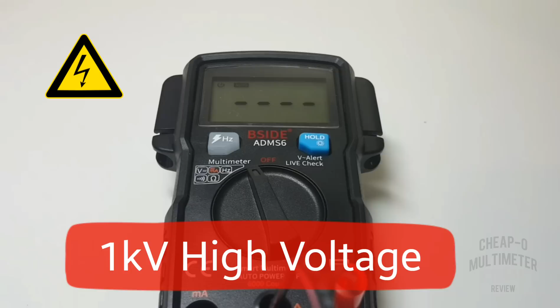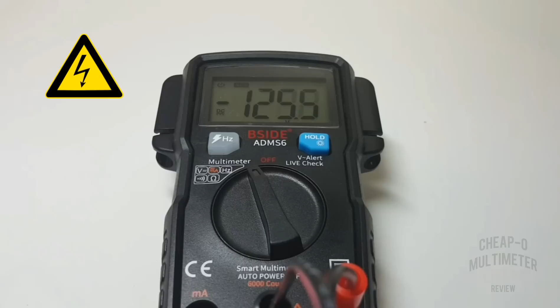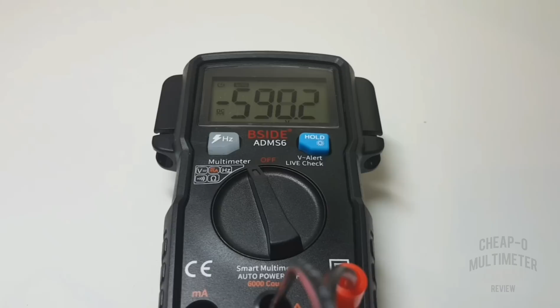Next, we're doing a high voltage test. We're going to take it up to about 1,000 volts, 1 kV. Let's see how the BSIDE can handle it, and whether we have a high voltage alarm or any audible indicator. Okay, here we go. We're getting an O-out, but there's no audible alarm. Try it again, and we are hitting that 600 volt threshold, but that is all she wrote. So it's able to take that high voltage without any snap, crackle, or pop. That's a good thing.